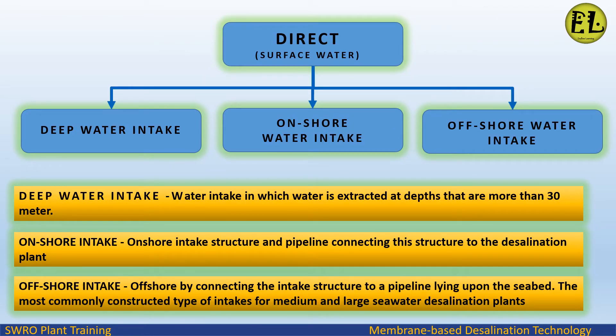Surface intakes are classified into three main groups: deep water intake, onshore water intake, and offshore water intake. Deep water intake extracts water at depths of more than 30 meters. Onshore intake uses an onshore intake structure and a pipeline connecting it to the desalination plant. Offshore intake connects the intake structure to a pipeline lying upon the seabed, and is the most commonly used type for medium and large plants.